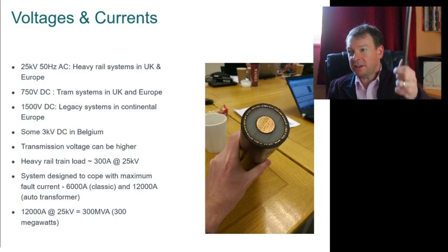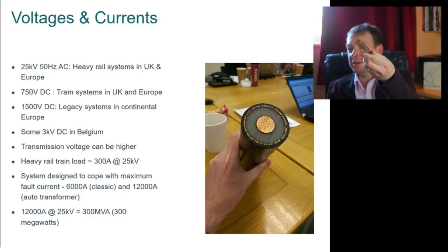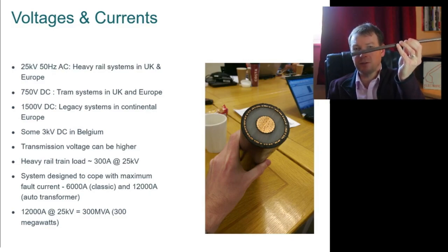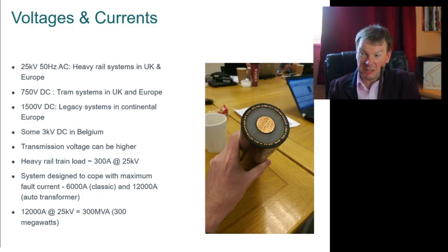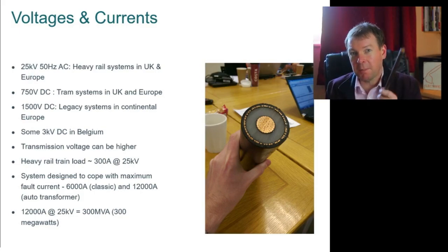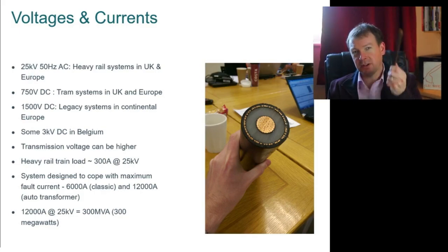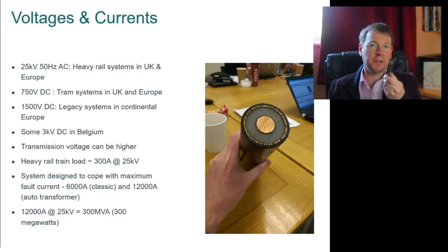So this is low resistance contact wire, I think copper silver, which has pretty low resistance and pretty high conductivity. The problem is there are materials that would have lower resistance, but they are softer and they stretch. Since you need to put the system under mechanical tension and it needs to resist the wear of pantographs for around 40 years, you don't want a soft material. So it's a balance. As I said at the start, this is about a balance of electrical and mechanical requirements.